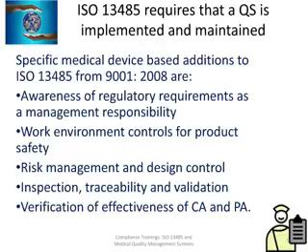And then the specific medical device-based additions to 13485, where did they come from? It came from ISO 9001, and as you know, ISO 9001 is used by many customers. Okay, it's used in 157 countries, with 1.9 million users, compared to 500,000 users for ISO 13485. But ISO 13485's parent is 9001, if you want to call it that.